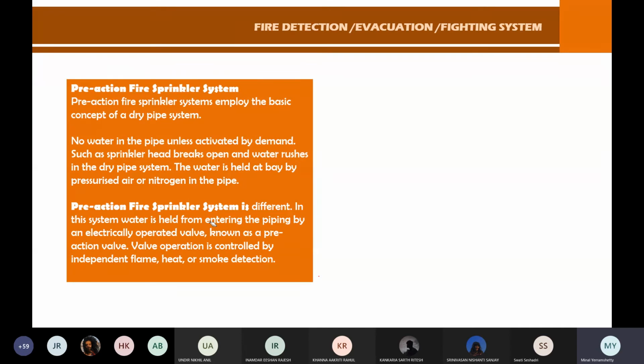It's called a pre-action fire sprinkler system. What does this mean? Very simple — it means I will not fill my pipes with water. I'll keep a dry riser. Basically it works on the same system as a dry riser. When there's a demand, I will attach something, and then the water will go. That's the system applied for the sprinkler as well.